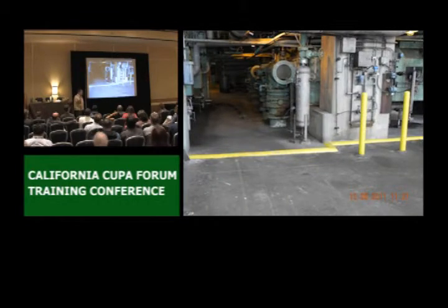This facility, they have a bunch of oil-filled equipment, and this is one of my power plants, right? Oil-filled equipment all on the inside of the facility. Everything inside drains to the separators, right? But just in case they had something sized, they poured these drive-on, drive-off berms around the entire operable unit. There you go. Perfect. That way if any of this stuff leaves, it stays in there.